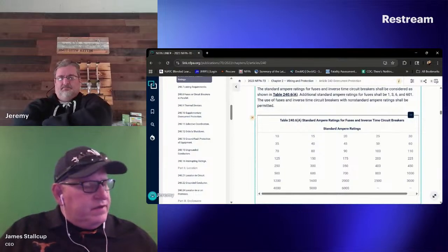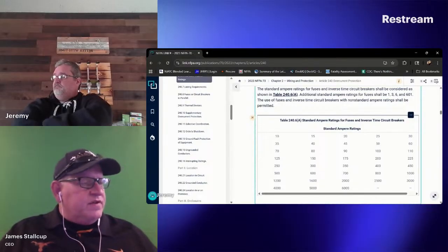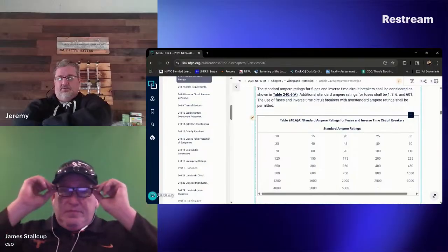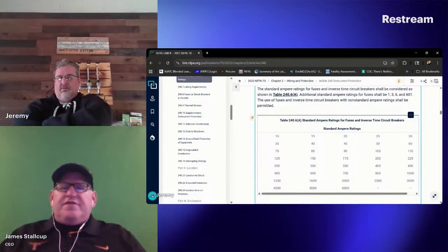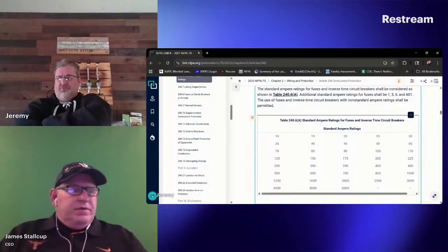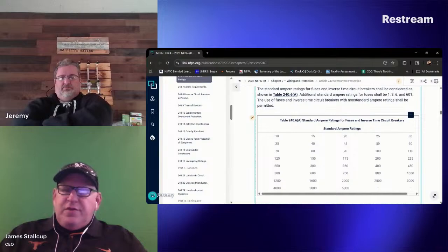1505 and then 310 times 5 is 1550. So that'd be 45 amps of difference. And I'd say you drop down to a 1500 amp, and what says you can't drop down to a 1300 or 1200? Well, I'm telling you what I added up.